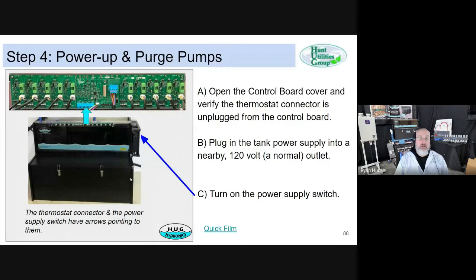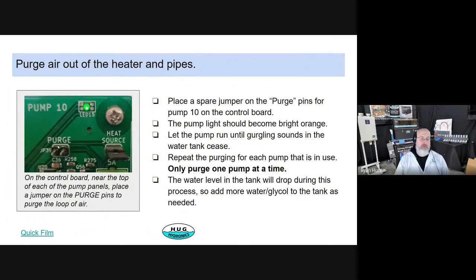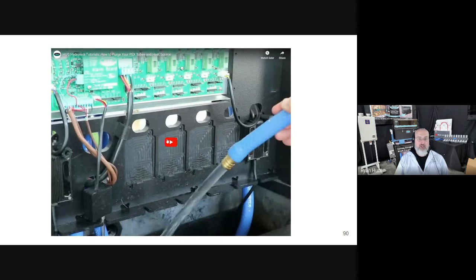Now we're going to power it up and purge the loops. There's a little more detail on that. At the top of every pump module in the control board, there's a module for each pump. There's purge pins. You just take one of the jumpers off, like the speed, and you bring it up here to the purge and it maxes that pump out. The little light above it goes to yellow, which means it's at max speed. And that's enough to fill the lines and flush the air out of it. It takes about 3 minutes on average, I think, to fully purge a line. But you just keep doing it until the bubbles stop, topping the water off as you go.